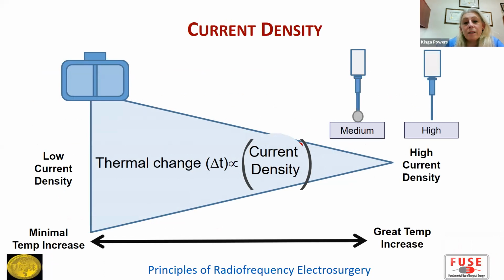It's a fairly easy concept: the smaller the contact area of your active electrode, like a needle-nose cautery versus a paddle, the higher the current concentration. The heat applied to the tissue is proportional to this current density, since the thermal change is proportional to the current per area squared. Always remember that equation, and you'll understand how you can achieve the same tissue effect using different edges of your instrument.